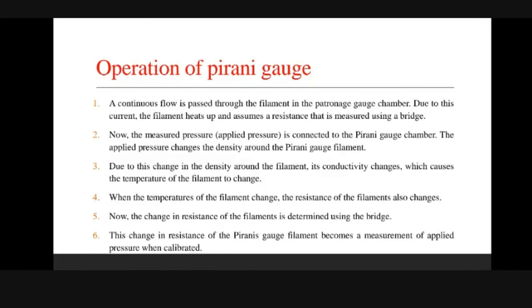Now the pressure to be measured is connected to the Pirani gauge chamber. The applied pressure changes the density around the Pirani gauge filament. Due to this change in density, its conductivity changes, which causes the temperature of the filament to change. When the temperature of the filament changes, the resistance of the filament also changes. Now the change in resistance of the filament is determined using the bridge. This change in resistance of the Pirani gauge filament becomes the measurement of applied pressure when calibrated.